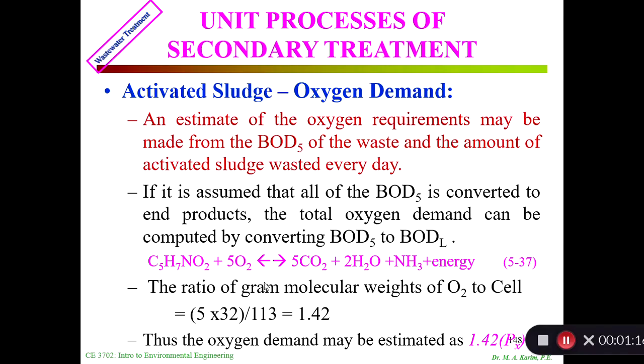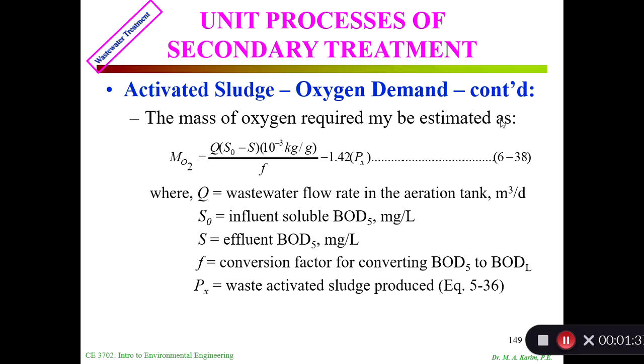The oxygen demand may be estimated by 1.42 times Px. Px is the wasted amount. Conversion from BOD5 to BOD ultimate is 1.42. The mass of oxygen required may be estimated as Q times (S0 minus S) times 10^-3 kg per gram divided by f minus 1.42Px. Q is the wastewater flow, S0 is the influent soluble BOD, S is the effluent BOD5.